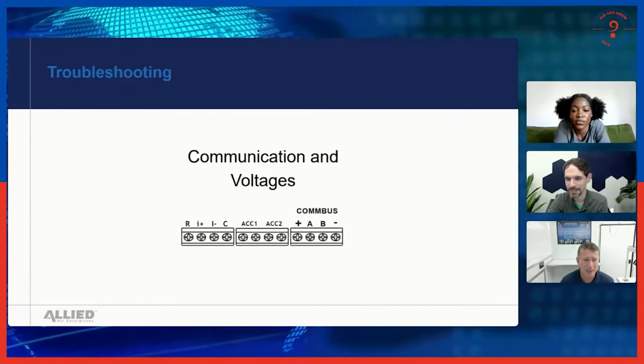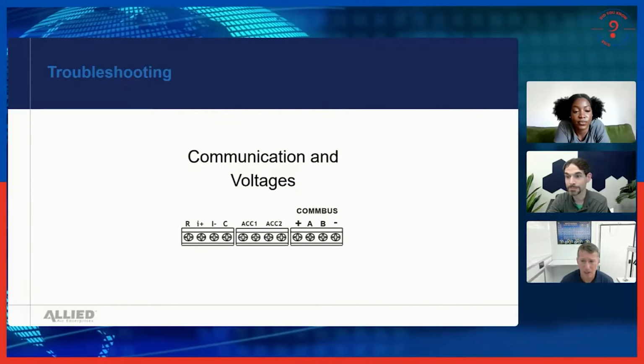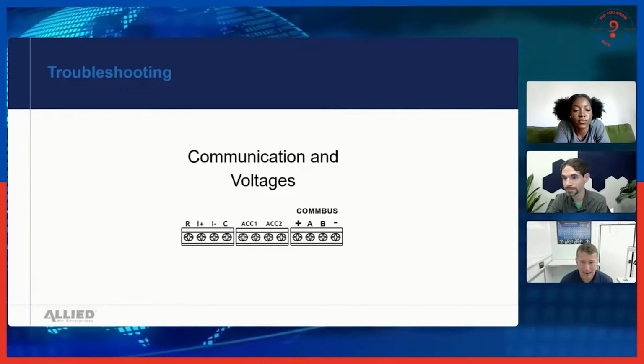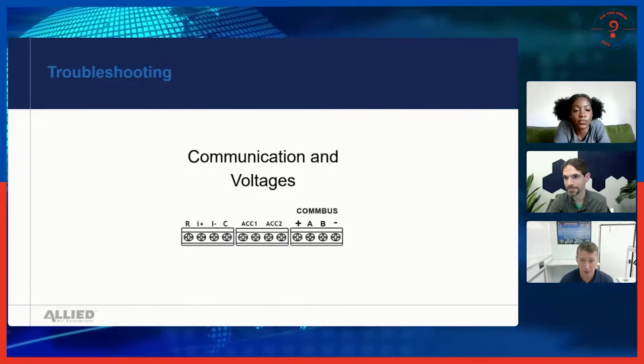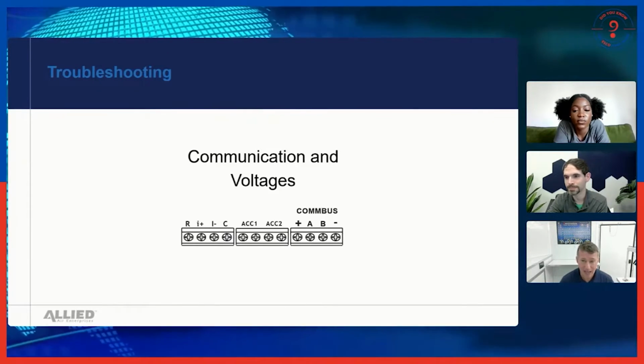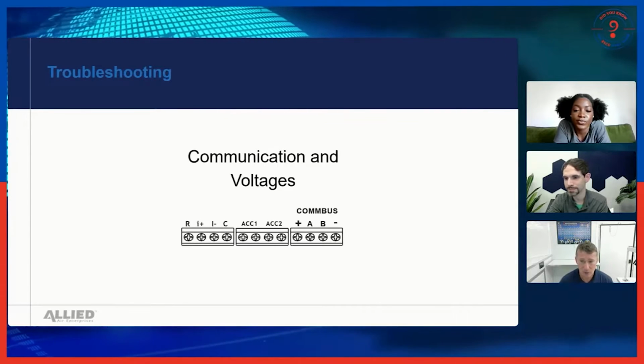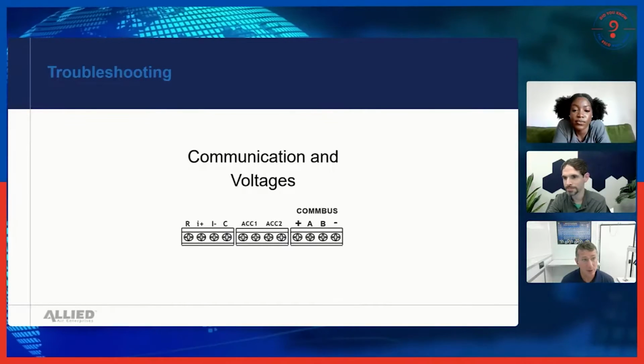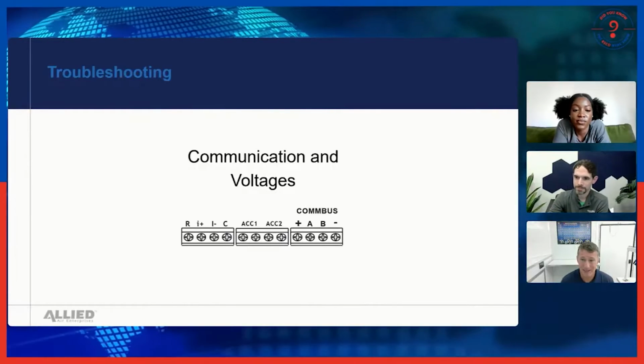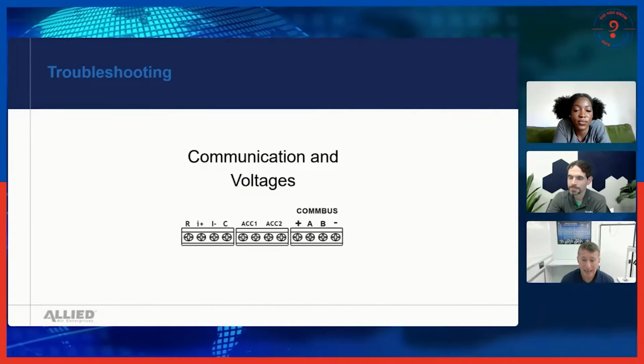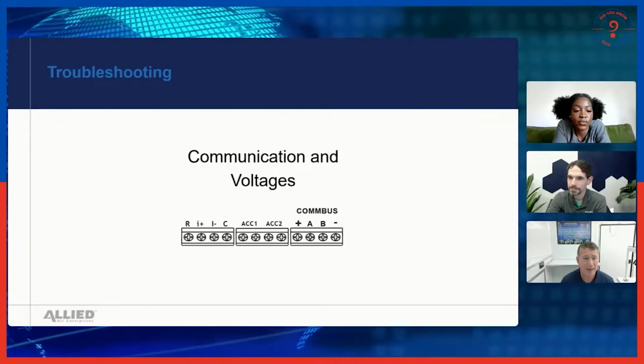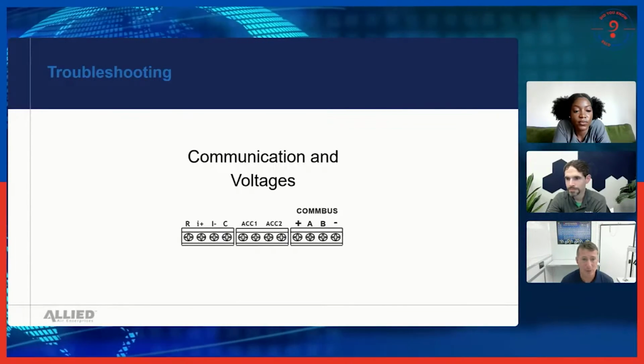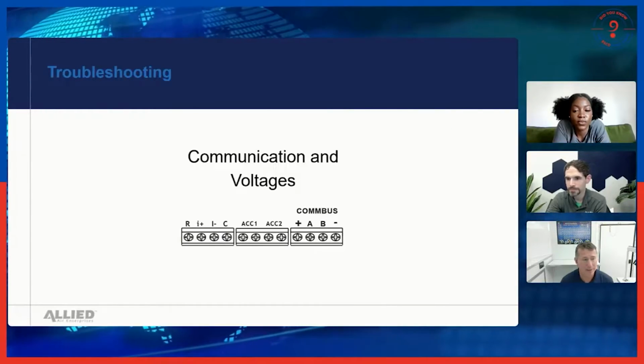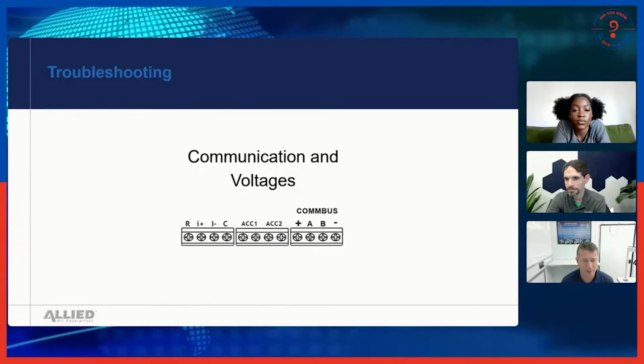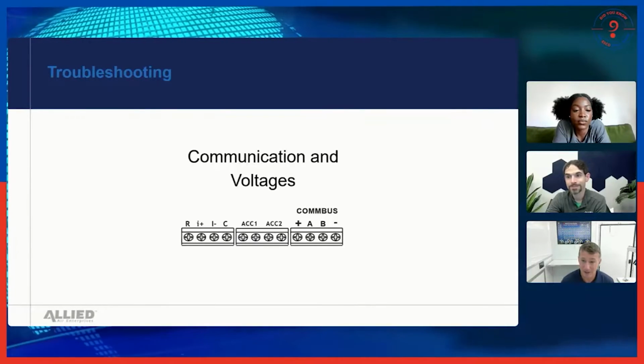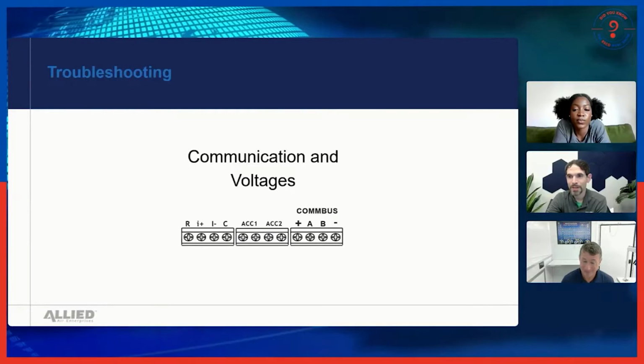Then they might go to positive or negative and find they don't have 24 volts there. Why not? That's because we're actually communicating, like a modem line or telephone line sending data back and forth. We're sending a data line so we can communicate. Now, it's not like we can put our meter on and read the voltages to know exactly what's being said, but we can understand whether we have a clear path for communicating, or something interfering that's causing things to not talk properly.